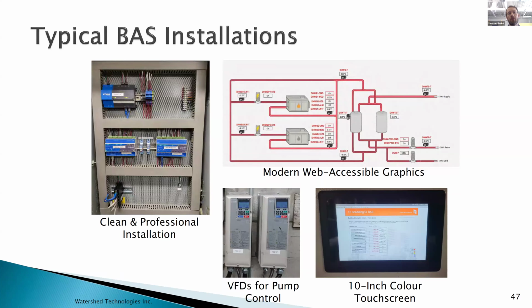These are just some pictures of what a typical building automation system installation looks like. We've got the building automation system panel, clean and organized. You have access to your system online, so you can log in and see what the boilers are doing in real time. It also sends you email alerts if there's a system failure. So if you suddenly have no domestic hot water, you can action that before your residents start calling. And as part of a building automation system, we're often installing variable speed drives on pumps or on makeup air units as well. And we like to put a color touchscreen display panel in the boiler room so that when your boiler techs go, they can access the system as well.